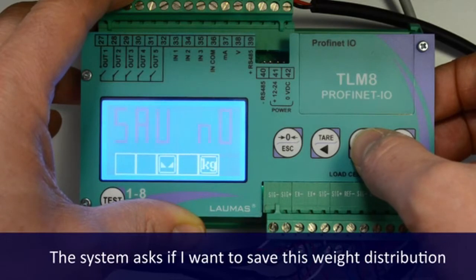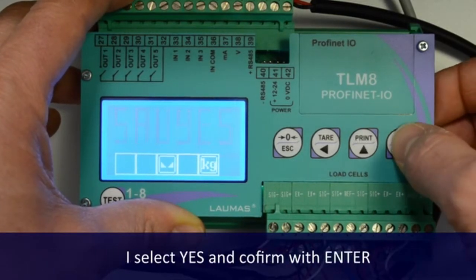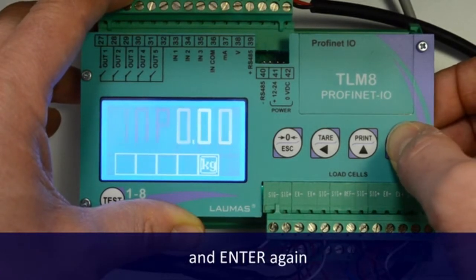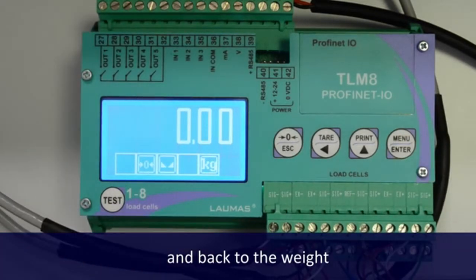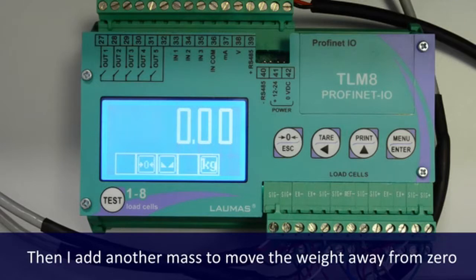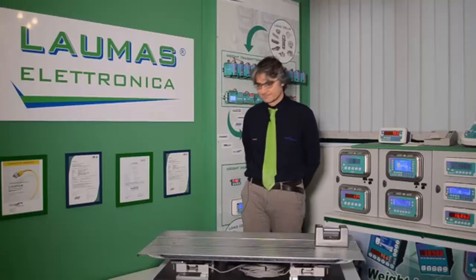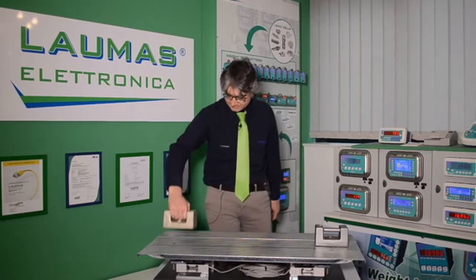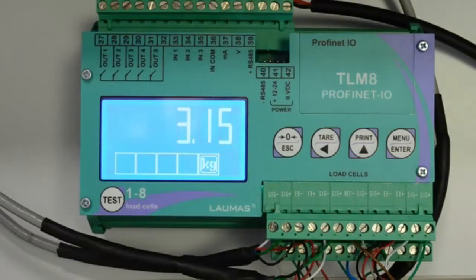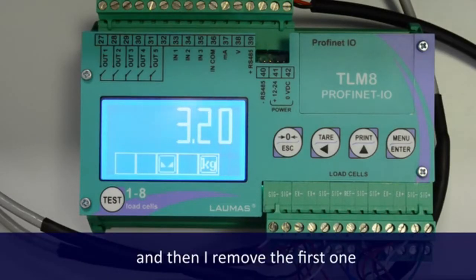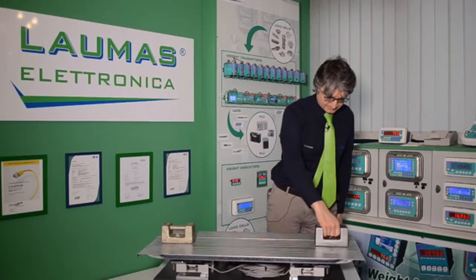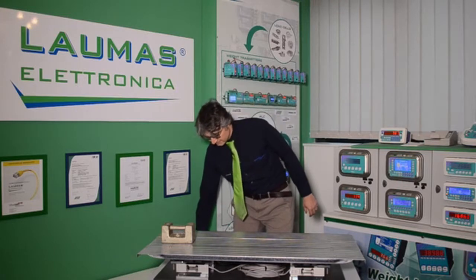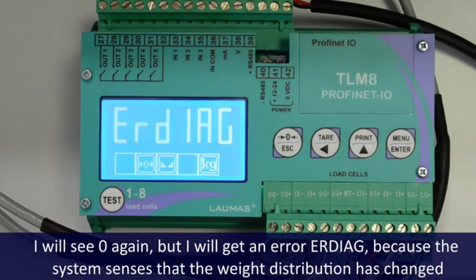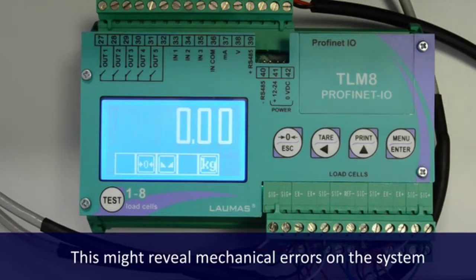Enter. The system asks if I want to save this weight distribution. I select yes and confirm it, enter. Then enter again, back to the weight. Then I add another mass to move the weight away from 0. And then I remove the first one. I will see 0 again, but I will get an error diag, because the system senses that the weight distribution has changed. This might reveal mechanical errors on the system.